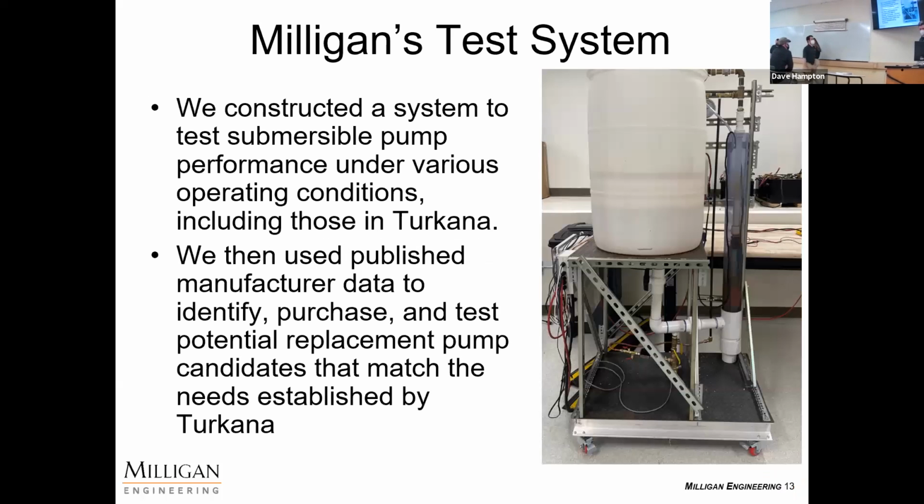So now to talk about our test system and how we started this project. Given these design specifications that CMFI gave us, we wanted to make sure that whatever pump we recommend would be able to meet all of their needs. And manufacturer data, while telling, is not always accurate. So what we started to do from the very beginning is build this testing system where we can verify all pump performance ourselves, so that we know the recommendation we give CMFI is an accurate one and that will be sustainable. So we went to the internet and we identified ideal pump candidates based off of the criteria, and we purchased them and we started to test them in our system.